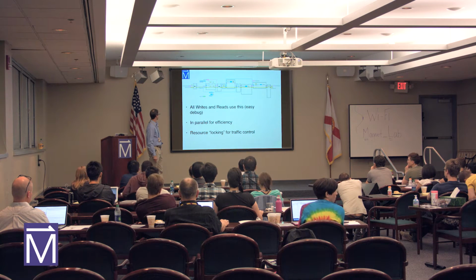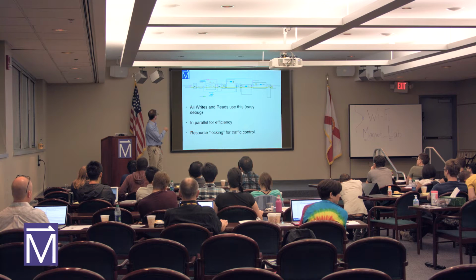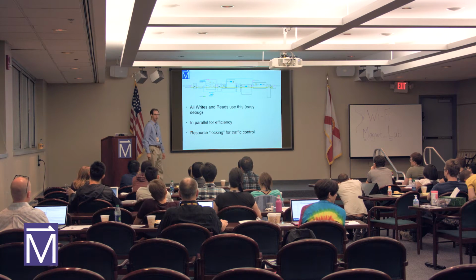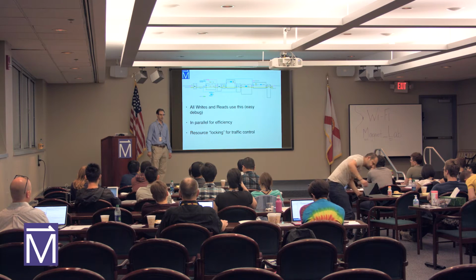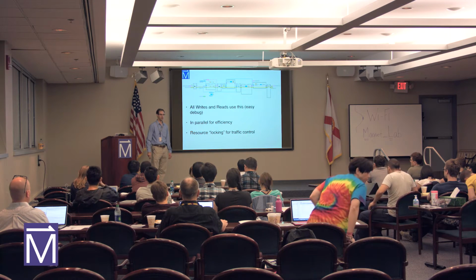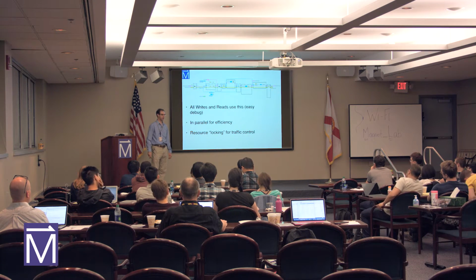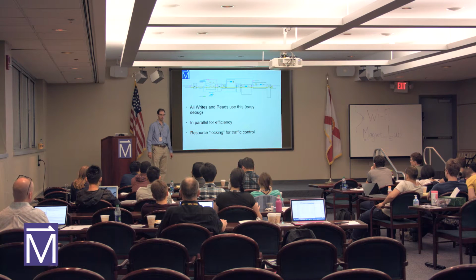Yeah. So all of these little stops and checks and timing bits and resets all take care of a specific class of instrument that behaves somewhat badly. And this is kind of remarkable, because with GPIB, every manufacturer has decided to do things a little bit differently. And so the challenge of having a single VI that talks to every GPIB instrument, including Oxford power supplies, which are particularly nasty, is really quite the trick.